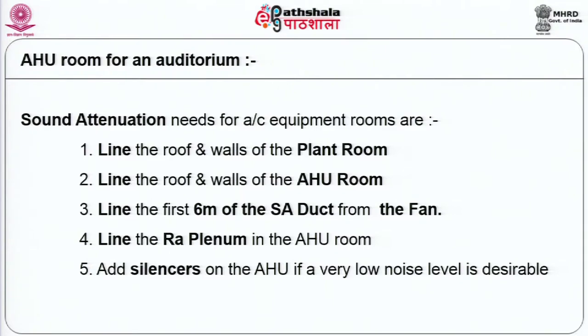to get the best out of your equipment. Having talked about two important parameters which identify normal air conditioning equipment and its placement in an auditorium, it does not mean that the normal factors which are done for normal air conditioning have to be overlooked. The normal factors are again very important, but the enforcement will be a little more rigid. In normal air conditioning for, let us say, a general office, if noise levels climb from 45 to sometimes as high as 55, people just do not notice, because hard floors and hard walls have become the order of the day. And if it has a hard ceiling like gypboard, the noise levels tend to climb, particularly in something like a call center application where audio is always allowed for and expected.